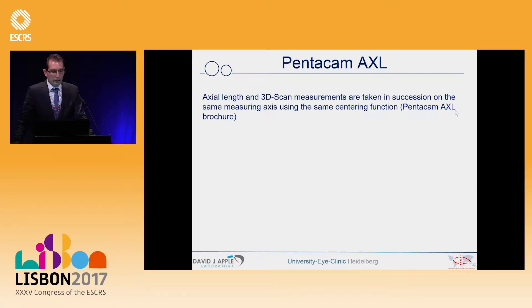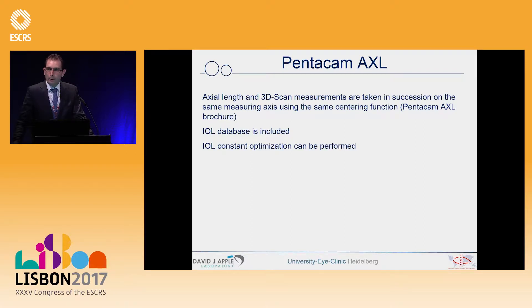The Pentacam AXL is used for axial length and 3D scan measurements, which are taken in succession on the same measuring axis using the same centering function. The complete available IOL database is included in the recent software, meaning IOL optimization can be performed on your side — you need only 50 cases for the regular formula, whereas for the Haigis formula, where the anterior chamber depth is very important, you have to add 150 cases for clear optimization of your IOL constants.